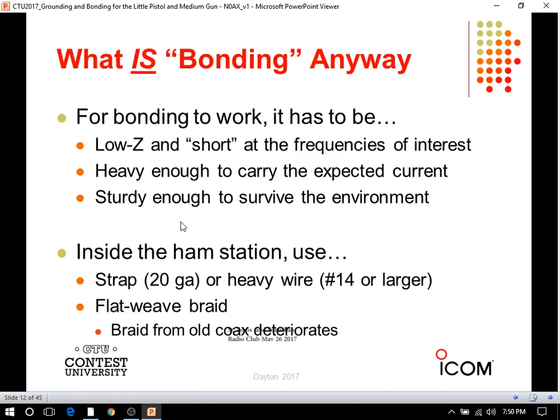That's why they require you to tie that conductor down, attach it to your framework or foundation—there's a lot of force involved. It has to be heavy enough to take that current without melting. This is lightning protection, not RF management, not the AC safety part. For RF management, you typically don't have very high currents. For AC safety, it just has to be heavy enough to trip your breakers. If there's a fault or a short circuit, the ground conductor trips the current protective devices, your breakers. And it has to be sturdy enough to survive the environment.